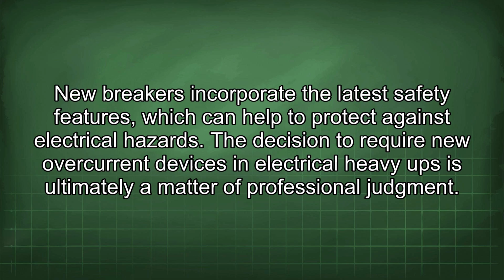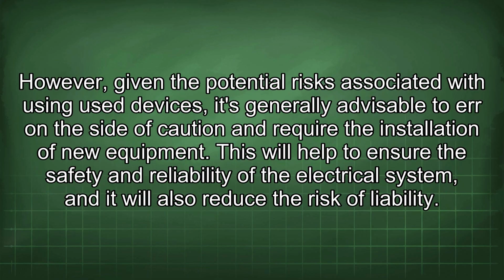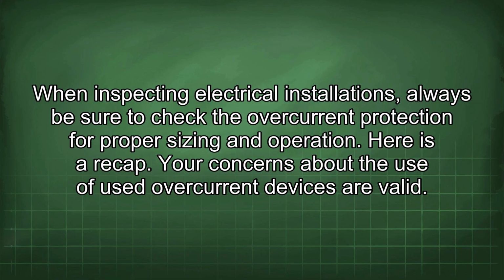The decision to require new overcurrent devices in electrical heavy-ups is ultimately a matter of professional judgment. However, given the potential risks associated with using used devices, it's generally advisable to err on the side of caution and require the installation of new equipment. This will help to ensure the safety and reliability of the electrical system, and it will also reduce the risk of liability. When inspecting electrical installations, always be sure to check the overcurrent protection for proper sizing and operation.